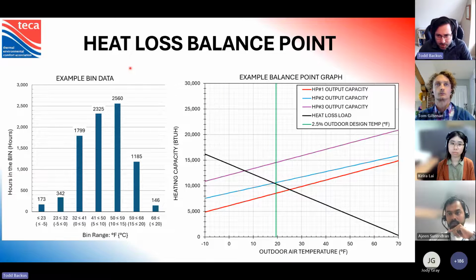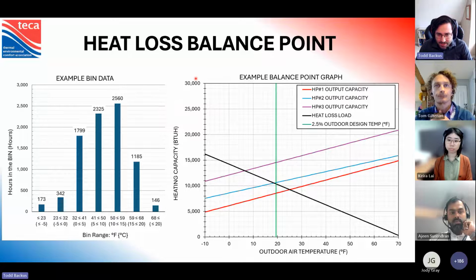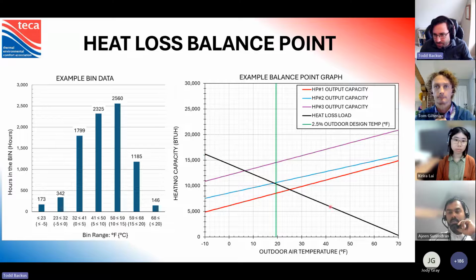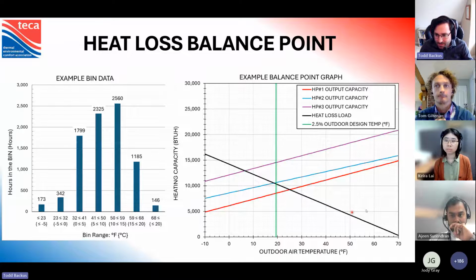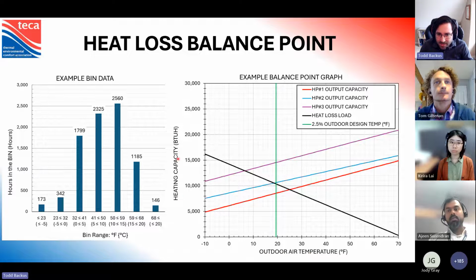I'm just going to touch on balance points for a moment. This does not get generated by the heat loss, heat gain calculator, but I use that calculator to generate this line here. So this line is the heat loss load of a dwelling. What we can see is we have our outdoor air temperature on the x-axis and our heating capacity in BTUs per hour on the y-axis. As the outdoor air temperature falls, the load on the building goes up. And that's because the delta T in those equations I showed at the start is getting bigger and bigger, which means this line is getting bigger and bigger.